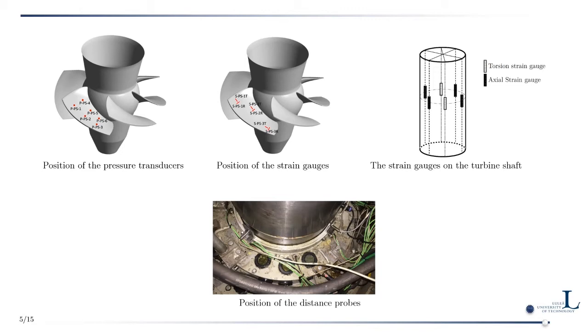In total, 12 pressure sensors were used — six on the pressure side and six on the suction side of the blade. Additionally, 12 strain gauges in three different radial and tangential locations were installed on both pressure and suction sides. On the shaft, four axial strain gauges and two torsion strain gauges measured axial load, bending in two directions, and shaft torque. Distance probes were positioned close to the turbine guide bearing.